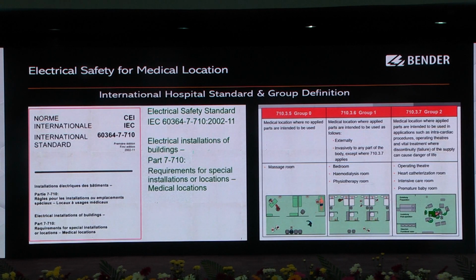So this is the standard IEC 60364-7-710, the electrical safety standard. It is mandatory for group 2 locations. And here you can see group 0 and group 1. Group 0 and group 1 are not mandatory for an isolation transformer or IPS panel. So you can use a residual current monitoring system.